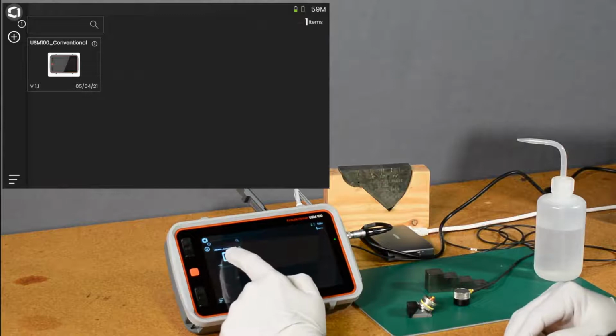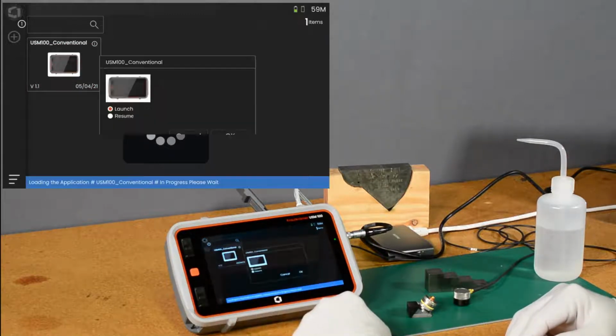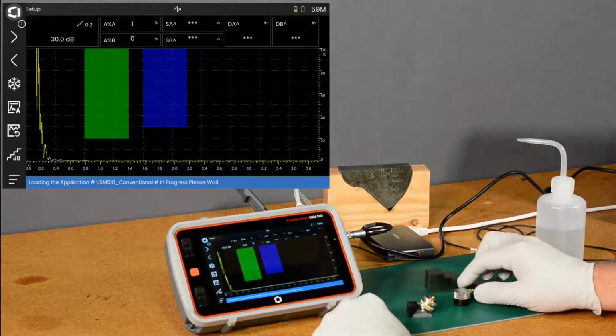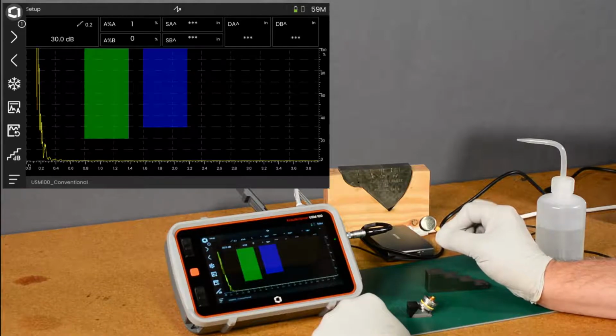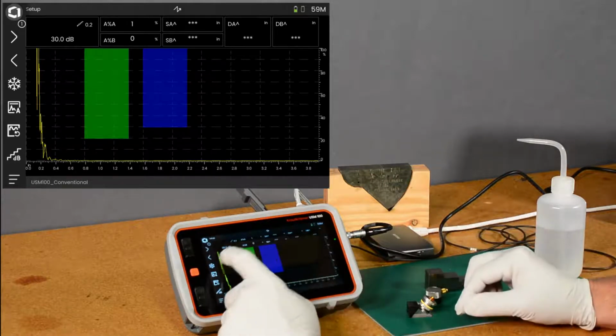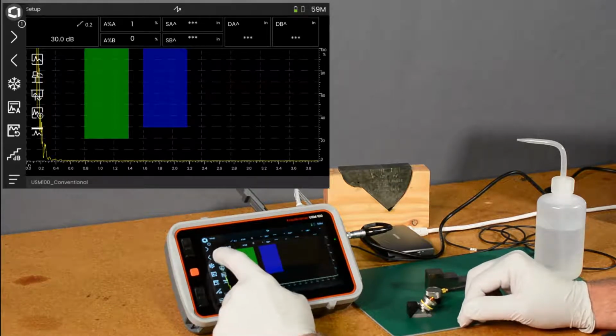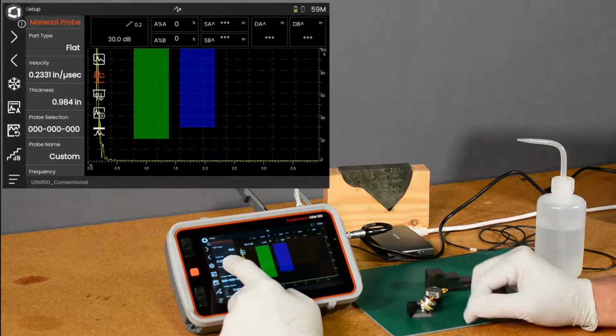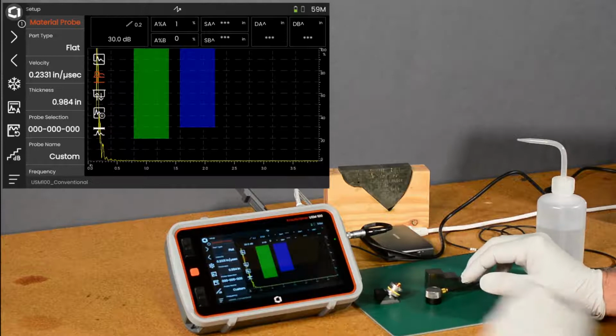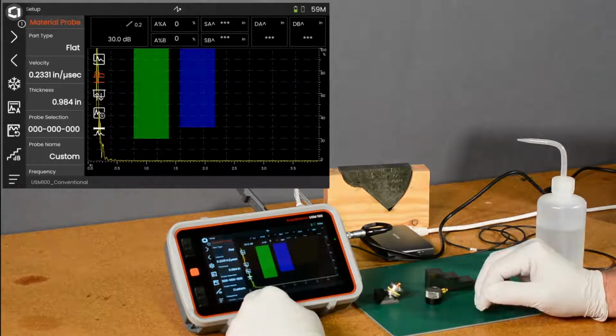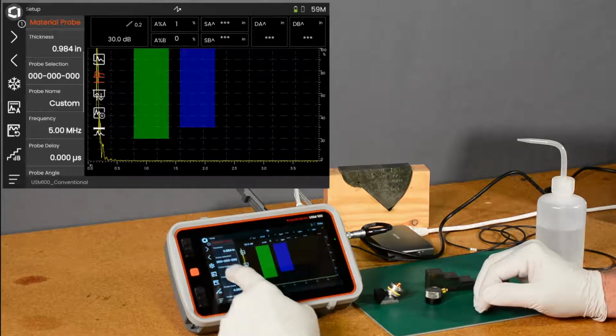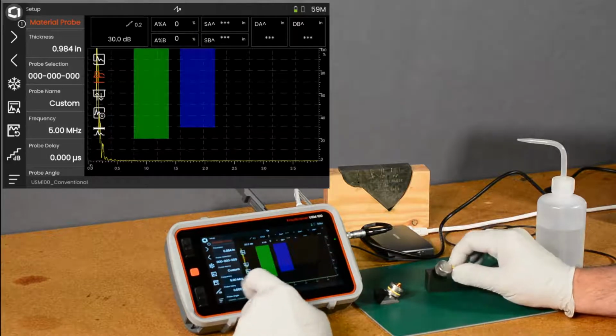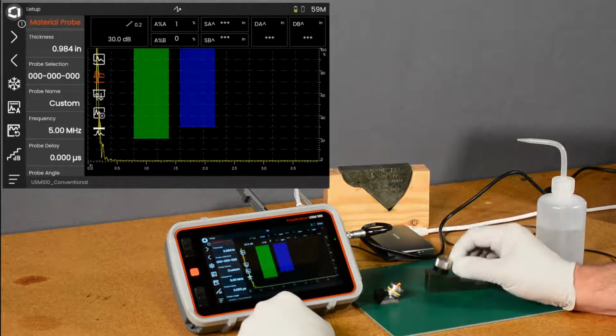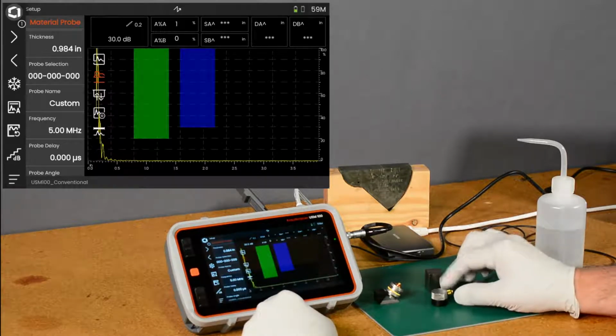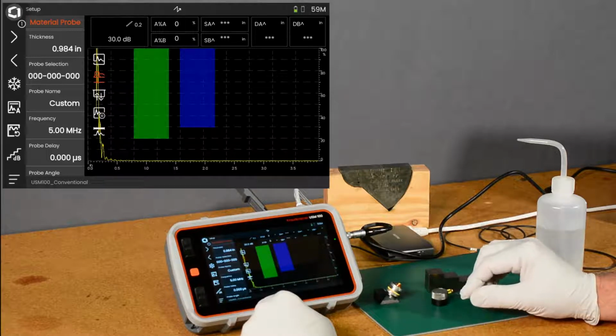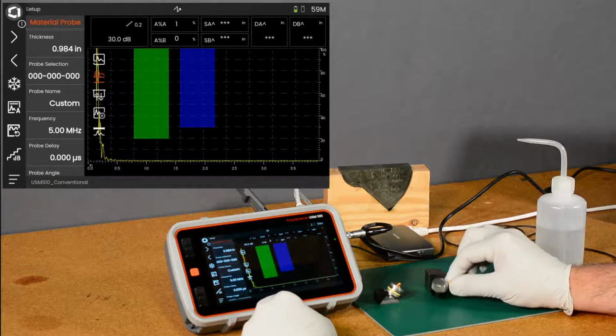Alright, so we'll start from scratch here. Launch our provided conventional app. Start from the beginning. I've selected a 5 megahertz gamma probe, so there's not a lot to change about the probe setup on this. The default value is already 5 megahertz, but we can come in here and look at the probe setup. Because we're going to be doing a straight beam calibration on a steel block, the default velocity of 0.23 inches per microsecond is going to be close. The probe frequency is already selected at 5 megahertz, so that's going to do a good job of setting the pulsar width. This frequency control in the probe menu deals mainly with the calculation of pulse width for our square wave pulsar, so optimizing the pulsar to work with the probe.